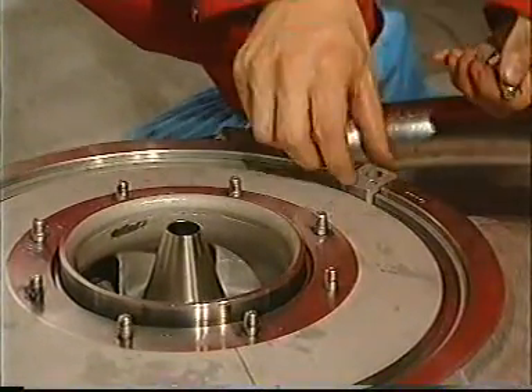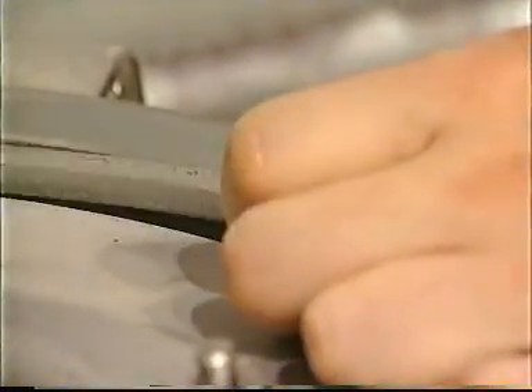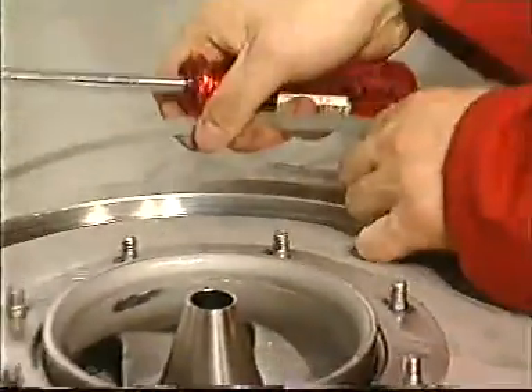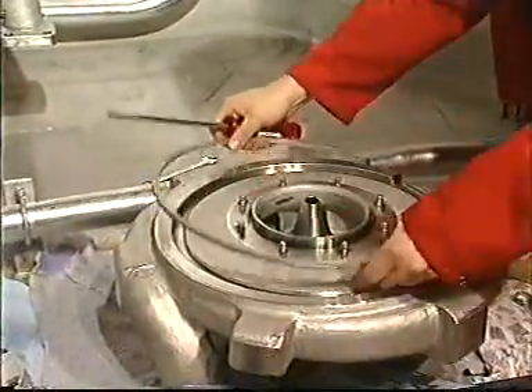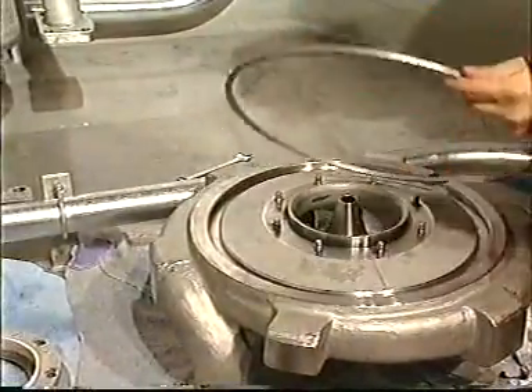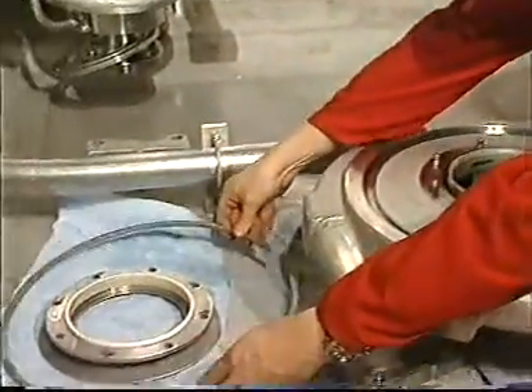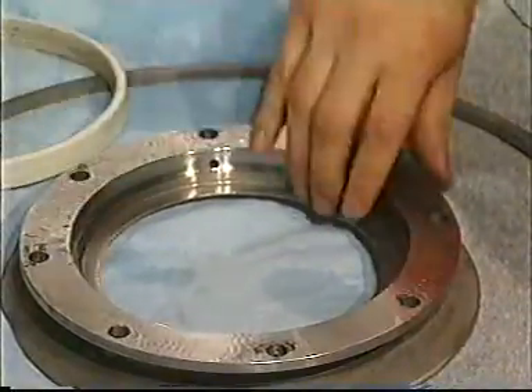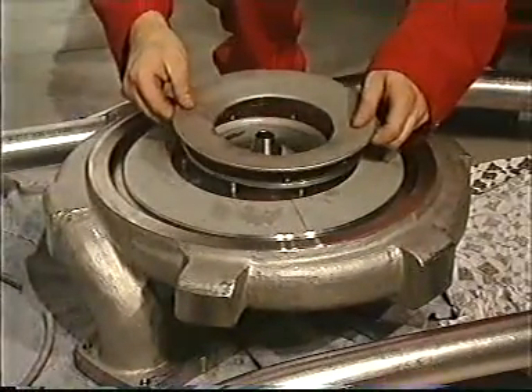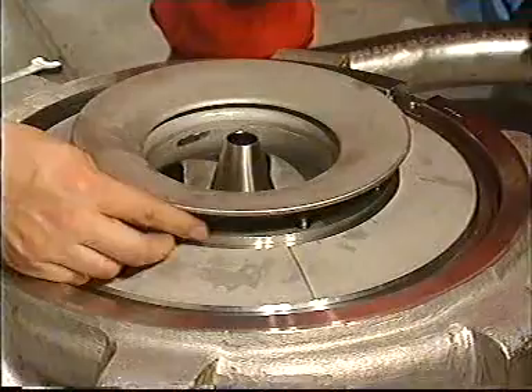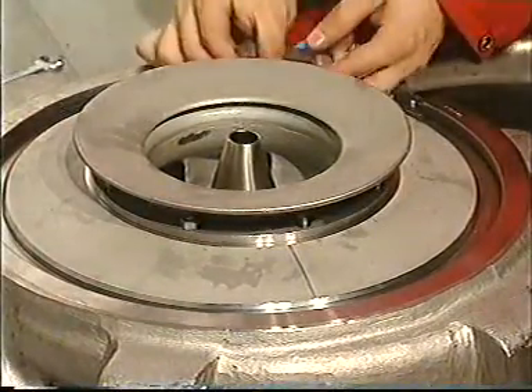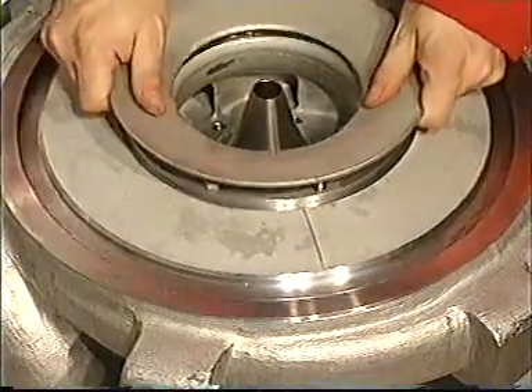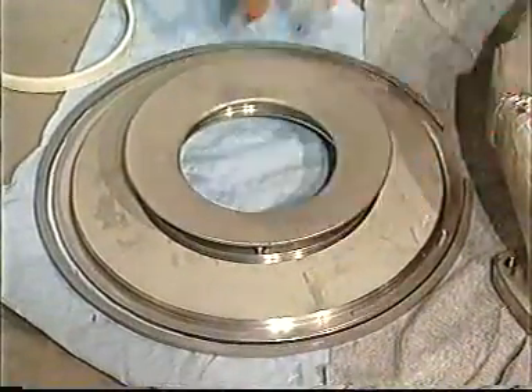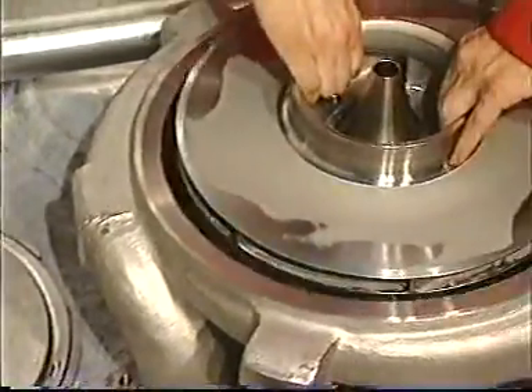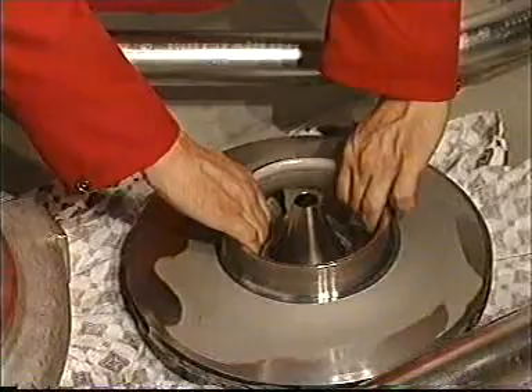Loosen the locking bracket and remove the locking ring. Use the suction bell mouth to lift out the suction cover. And finally, lift up the pump impeller.